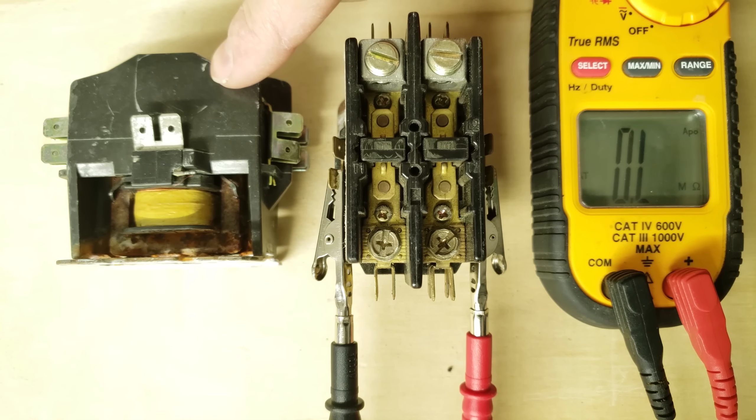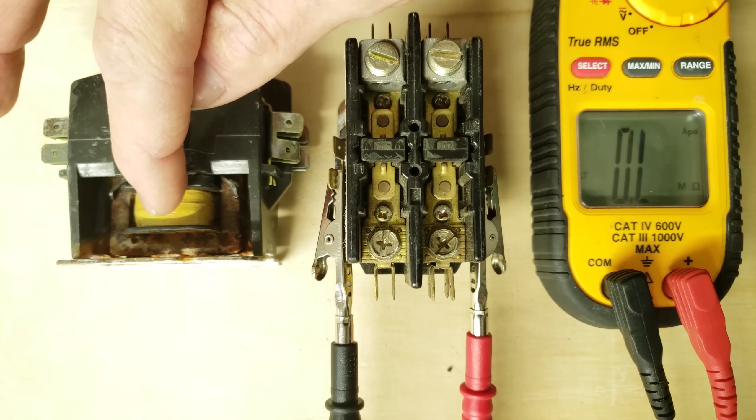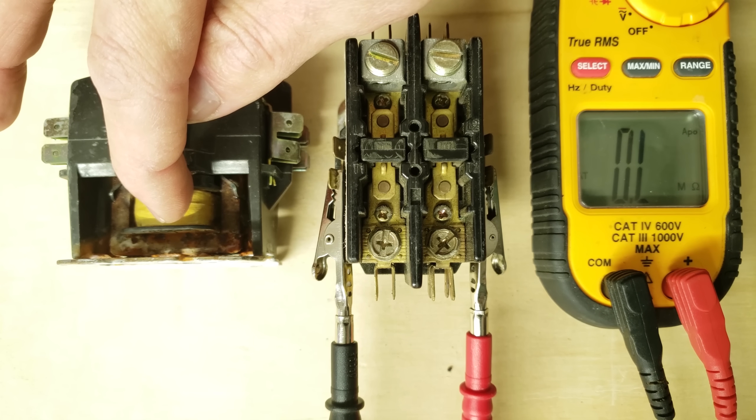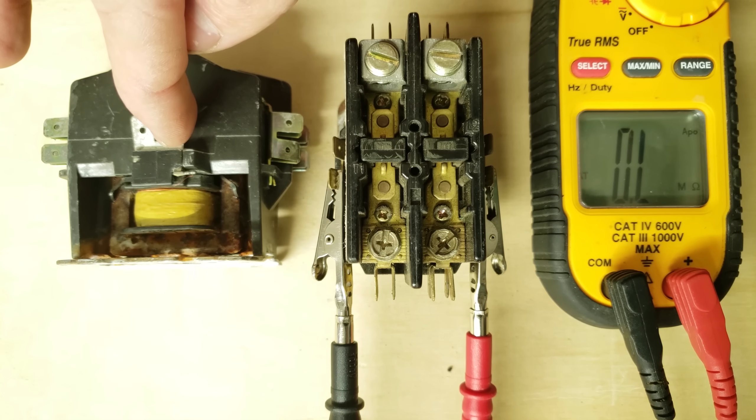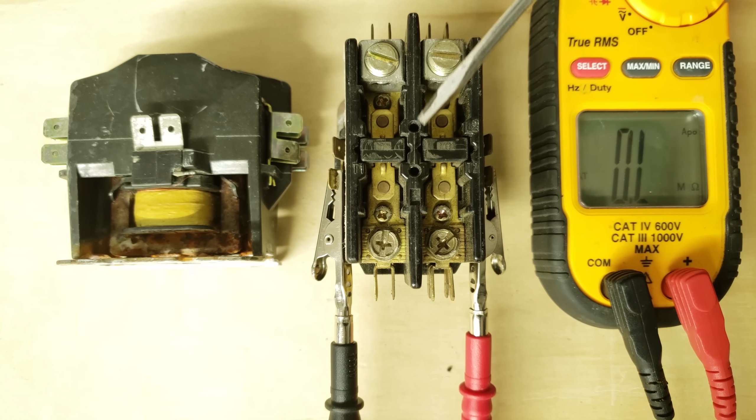In this case this one had a little puddle of water from the bottom up to the bottom of the coil and that shorted this coil out. So in this case you would need to replace these contactors.